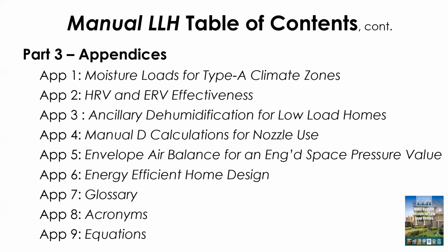And then lastly, part 3 is the appendices. It gives you more information about the moisture loads for type A climate homes, which would be Charleston, South Carolina, or Homestead, Florida, places that typically have really high moisture loads, the southern Gulf shores and where have you. It goes into more detail on HRV and ERV effectiveness, because a lot of times we'll select an HRV or an ERV based on airflow and not look at the effectiveness of it. And the effectiveness has more of an impact than the airflow does, because you may need to pick a different one based on the fact that it's not as effective as a different kind. It talks more about ancillary dehumidification for low load homes and how to select the right dehumidifier and how to utilize it.